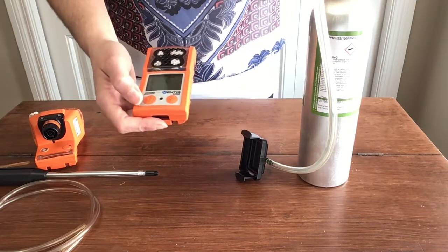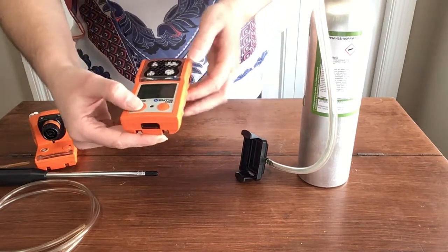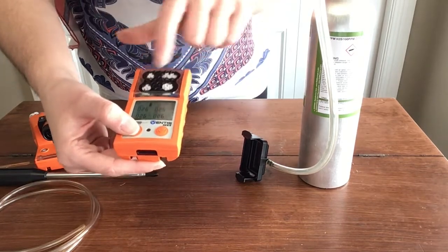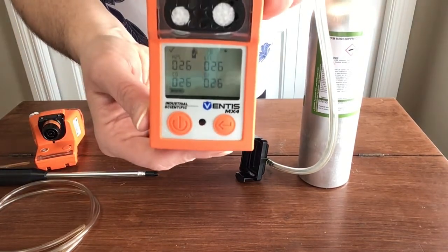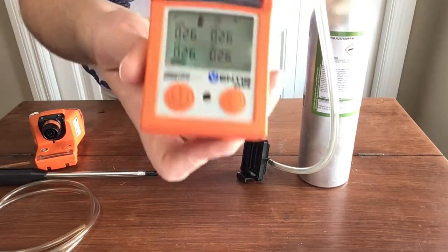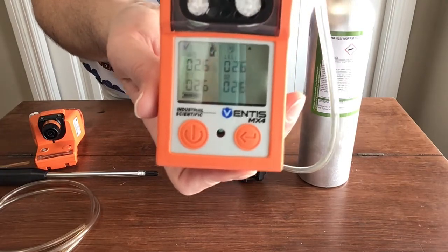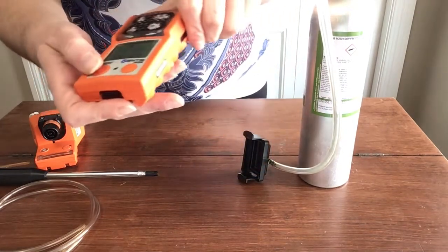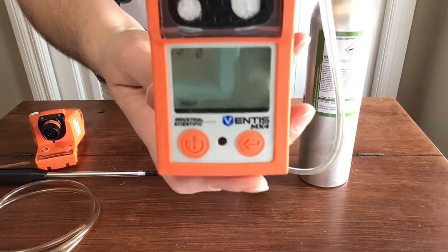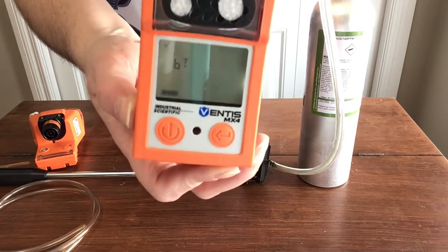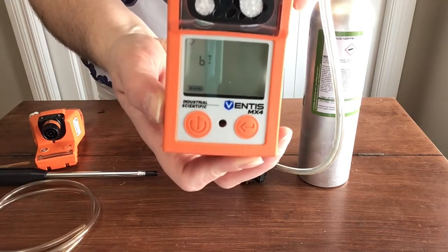And the way that you know whether you can do that or not, if we start moving through our screens here, so we can see here, this is the screen I was talking about earlier that tells us we have 26 days left to calibrate. You see that little cylinder at the top, you see the little calendar right here, okay, and 26 days. This is our screen for our fresh air zero. Press mode again. This is your BT, your bump test screen. You wouldn't be able to see this through your mode button if you didn't have it configured properly.